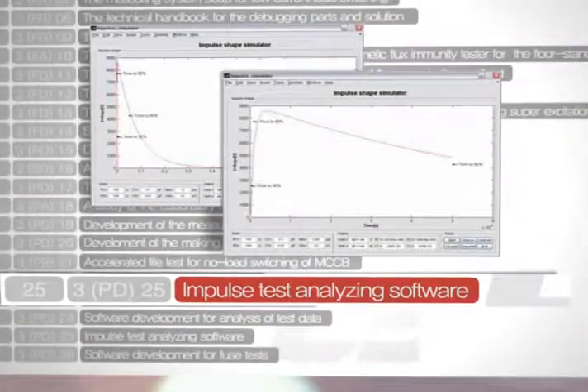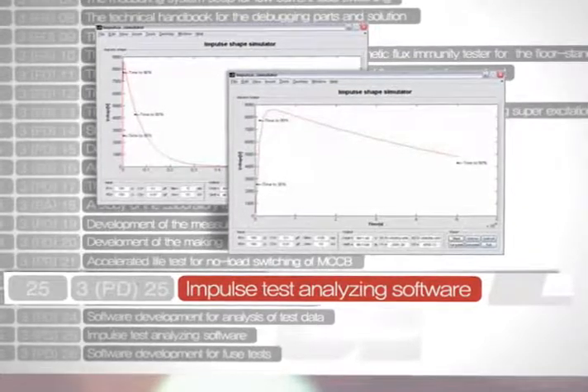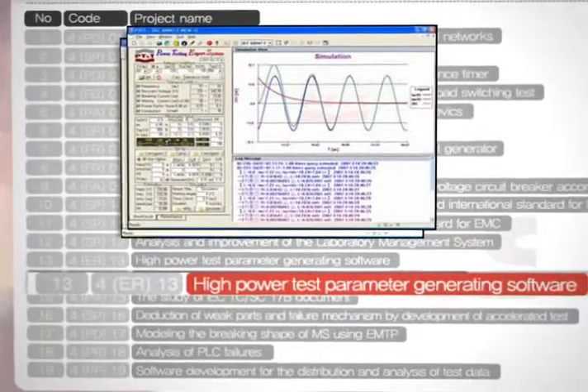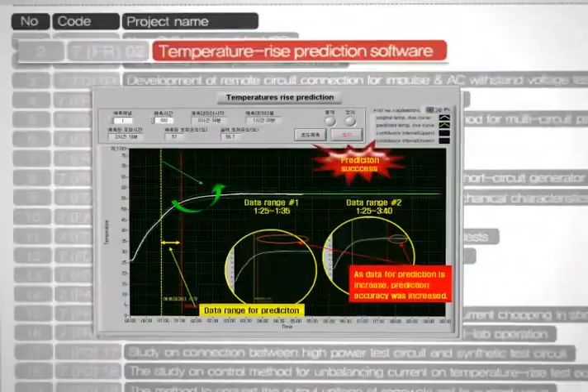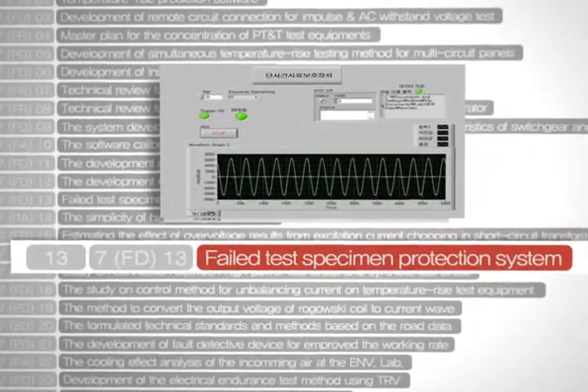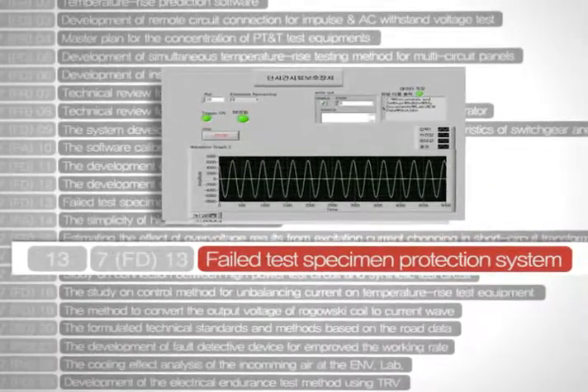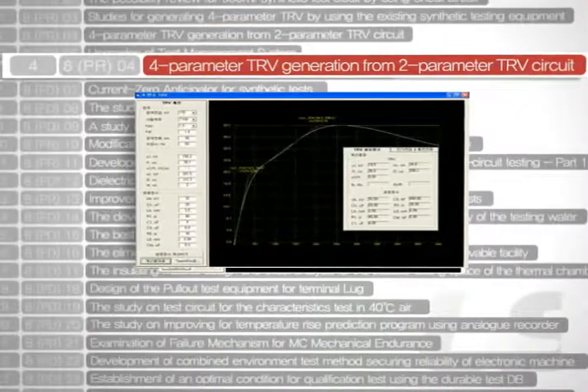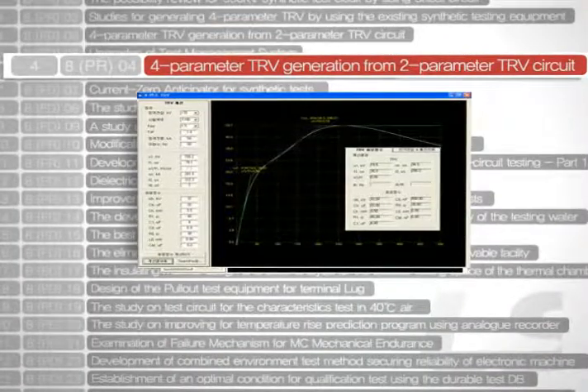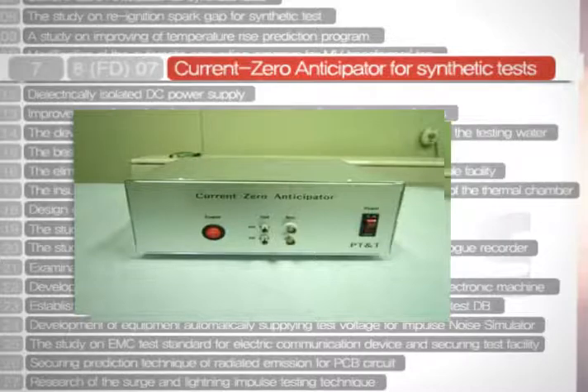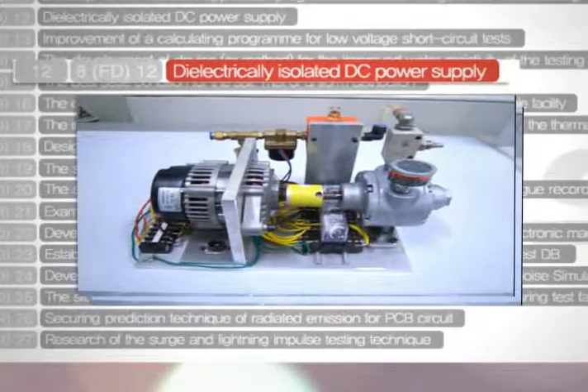In addition, we have developed a lightning impulse test software program, high-power test parameter generating software, temperature rise prediction software, and an apparatus to save the failed test piece for its failure analysis. In addition, we have developed 4-parameter TRV generating method from 2-parameter TRV circuit, a current zero anticipator, and a dielectrically isolated DC power supply.